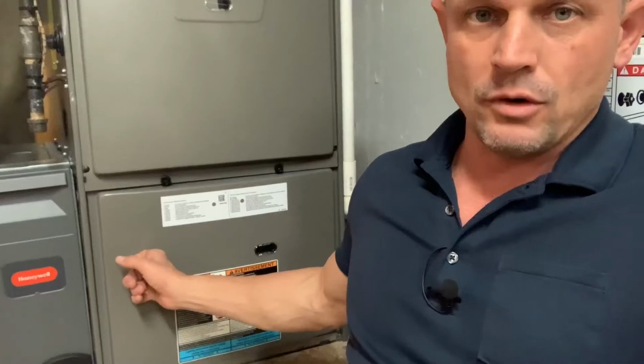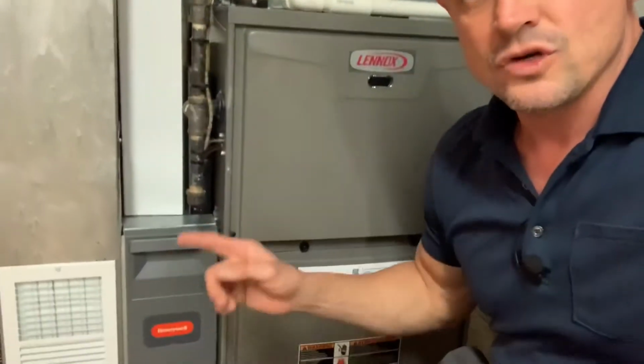And why we say to do that is because the more restrictive it is, the more stress it's going to put on the blower motor. We want to try to maximize the longevity of the furnace. I typically tell people to buy a dozen of them. Put a reminder in your phone, check it once a month. If it's clean, just let it ride. Another little tip, if you change out your furnace filter and you're still having issues, turn the service switch off.